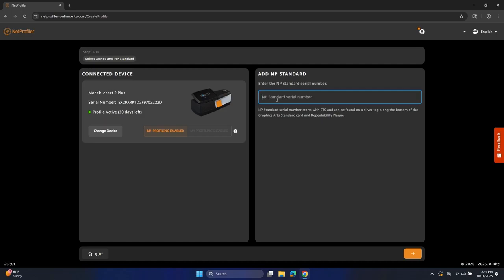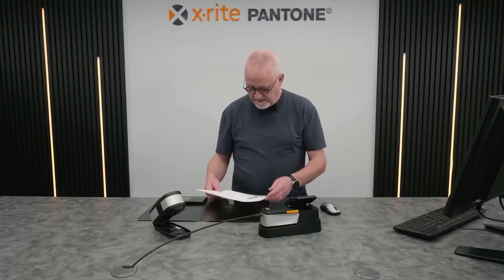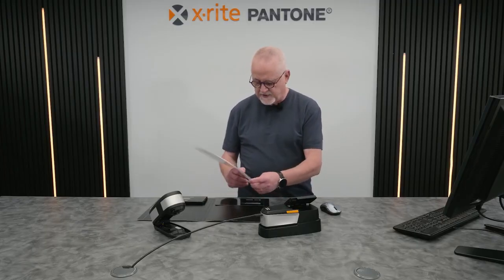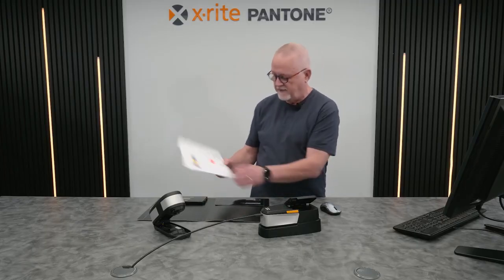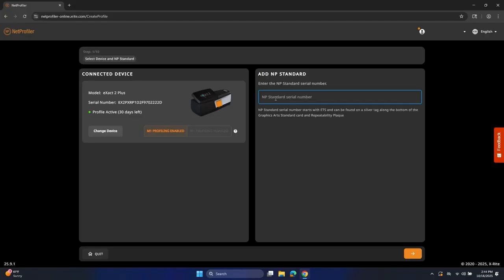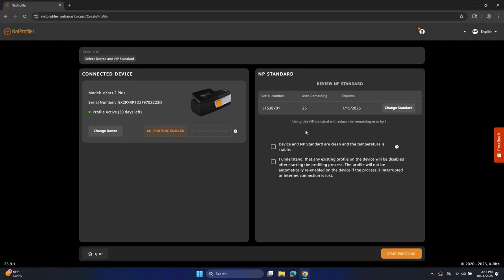The next thing I have to do is tell it its NP standard serial number, which is on a little sticker right here on the card. Okay, and I can see it is ET538701. Okay, when I hit the next button, it's searching for that standard, and it's going to say, yep, it found it. These cards have a use limit, so it has 25 uses remaining.